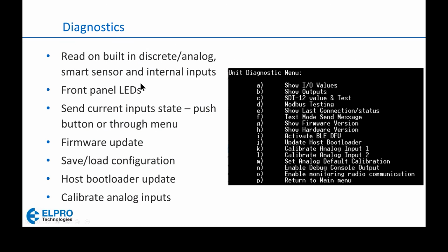Okay, and here we go. Last slide for today. This just shows you all the diagnostics that we've got inside the radio system. You can read the analog or discrete inputs directly off the radio. You can look at the front panel LEDs to figure out if the unit is in alarm condition or not. You can push that button on the front panel to force it to transmit all the values to see if the SCADA system gets the update.